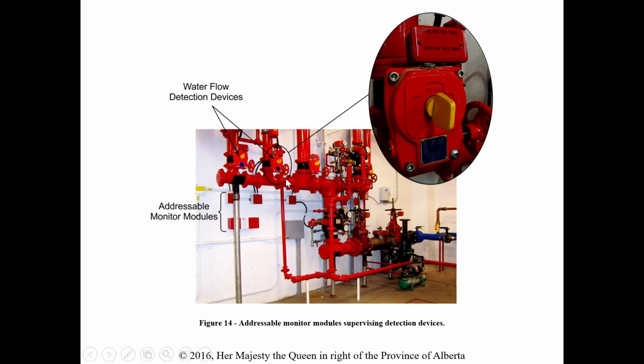Then it starts talking about the different devices that we can attach to our system for pieces of equipment that don't have an address. So if we have an addressable system but we have a pump or a flow switch or even a signaling device that's not addressable, you can use those devices in an addressable system with supporting field devices. So they're monitor modules, signal modules, or control modules. Basically what it does is give an address to a piece of equipment in the system that doesn't have one, so that the system knows that it's there and can control it, or potentially just know on a supervisory issue, depending on what type of module.